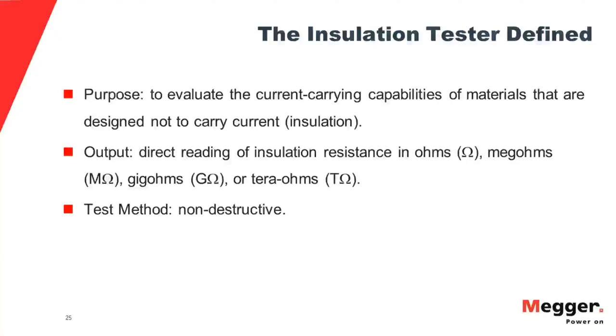and make sure that it's maintaining its maximum capabilities and that your electrical equipment is still functioning properly and is safe. And note, we now have direct reading. All the old manipulation is gone. You select a test voltage and it's simply a matter of a selector switch position, and you get all the information you need. We measure up into teraohms. I'll talk about that a little bit later.